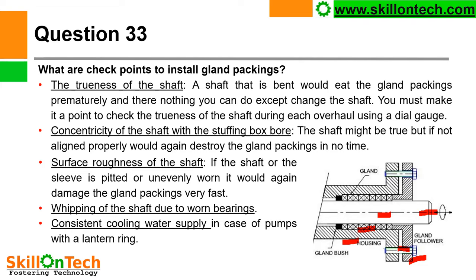Whipping of the shaft due to worn bearings. If your bearings are worn out, then your shaft may not rotate perfectly in the center, and that may also cause wear of gland packings. Consistent cooling water supply in case of pump with lantern ring: if a lantern ring is provided in the gland packings, then a continuous cooling water supply is required. Due to friction, gland packings get heated and due to high temperature rise, gland packings may damage very fast.